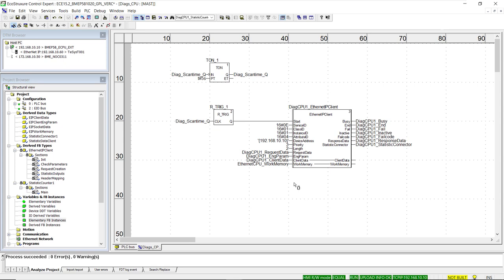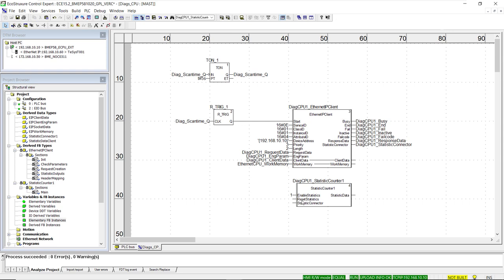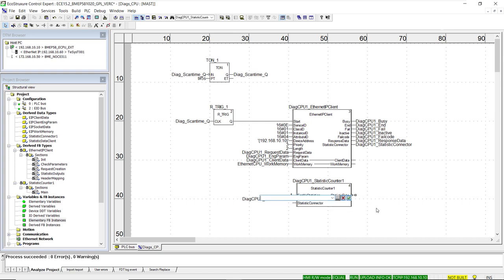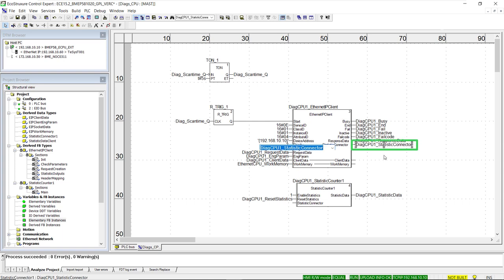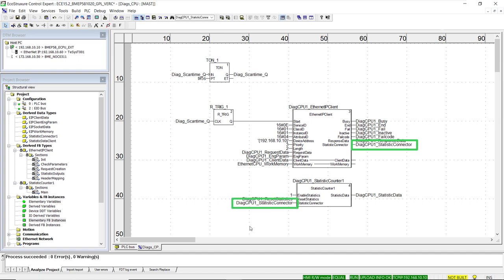We add the prefix diagcpu1 to the statistic counter instance name, then create variables for input and output pins following the same convention. The way to interconnect the Ethernet IP client with the statistic counter function block is to use the variable name created on the output pin for the statistic connector of the client function block, and type that same name at the input of the statistic counter function block.